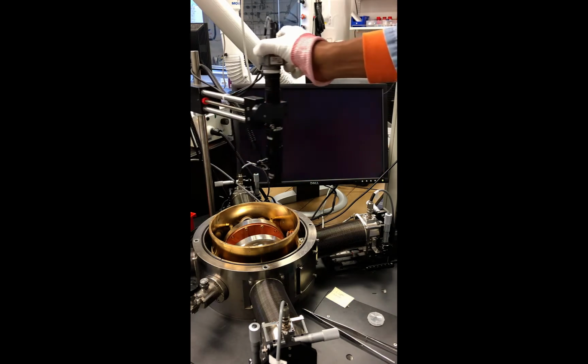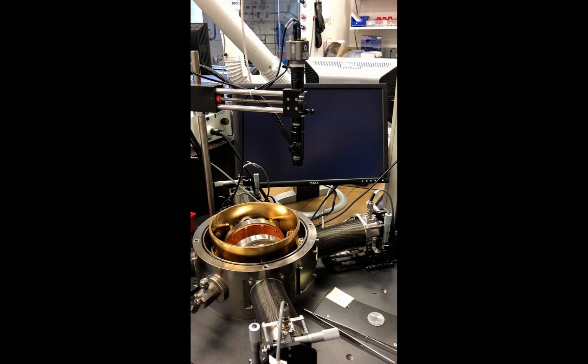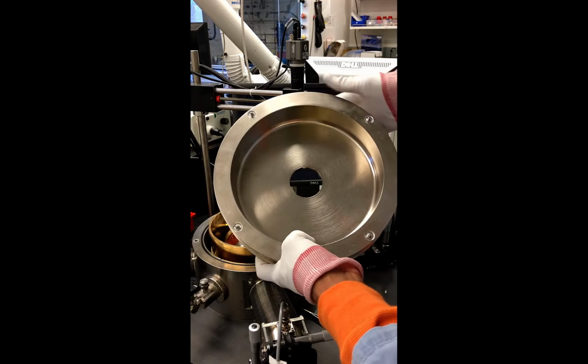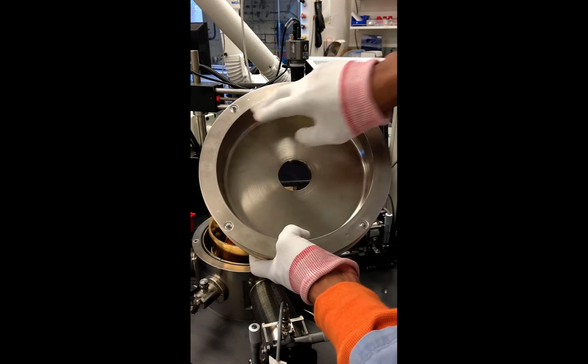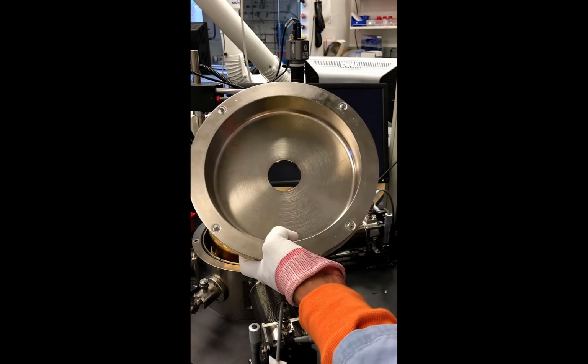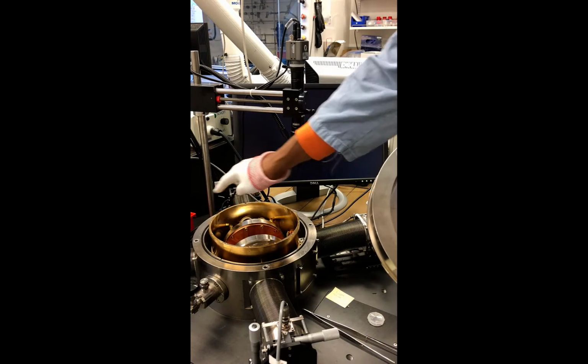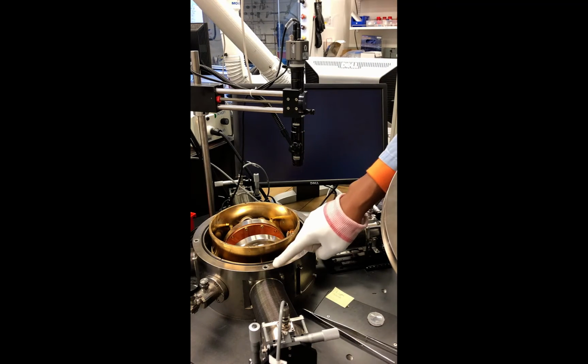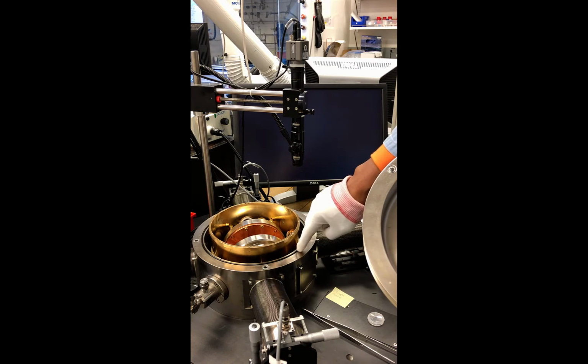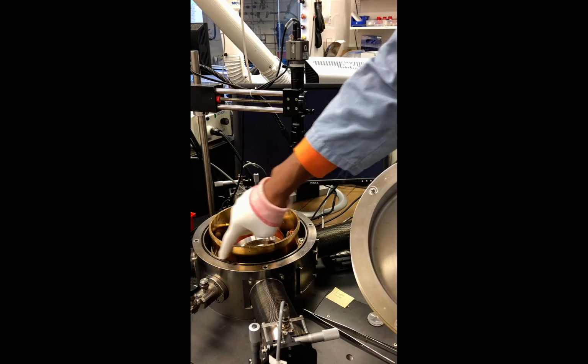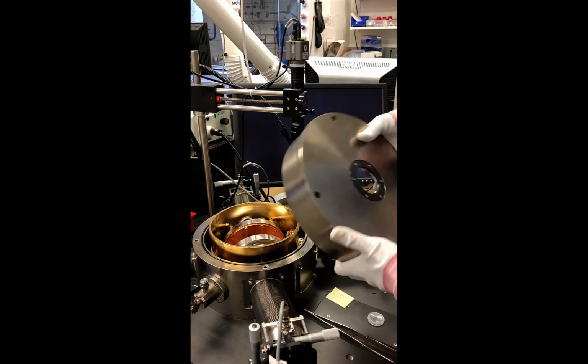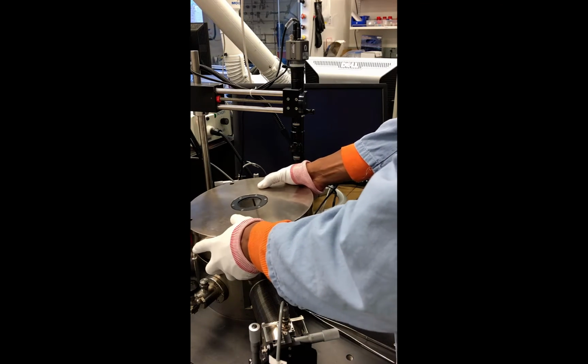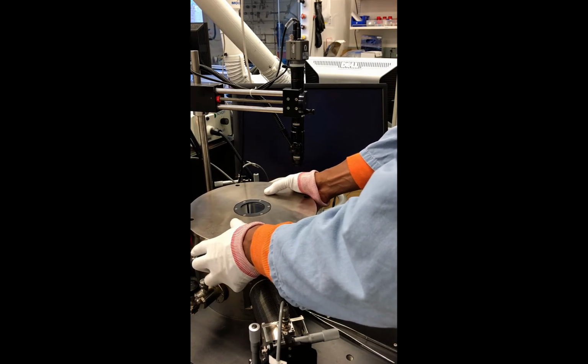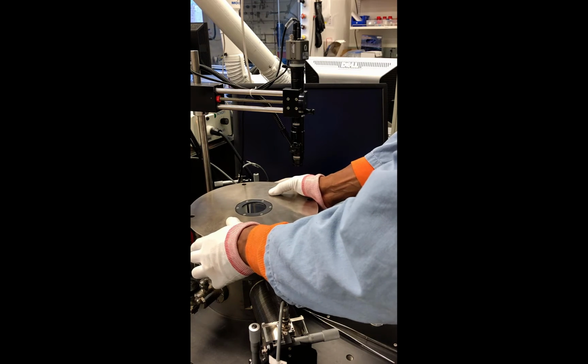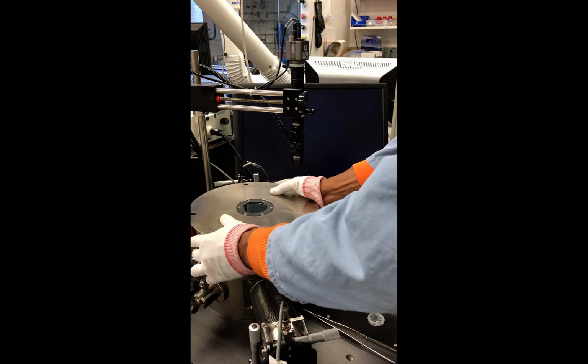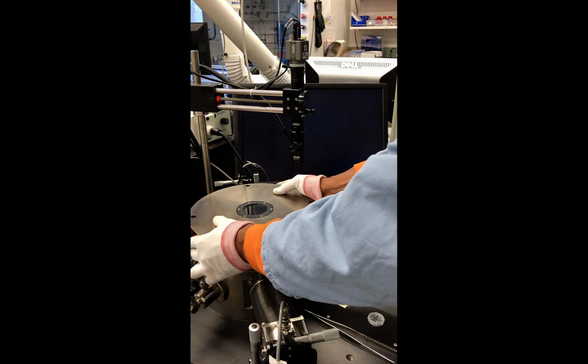Now we can close the chamber. When you grab the lid, notice the 4 pegs around the edge. These pegs must align with holes that you'll see on the chamber to correctly position the lid. Before you close the lid, also check the O-ring to make sure that it is free of debris. Otherwise, it will be difficult to pump the chamber down later. Sometimes it takes a little patience to lock the lid in place, but you'll want to make sure it is in place before continuing.